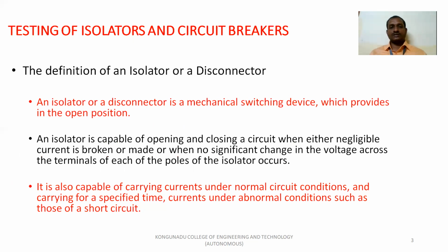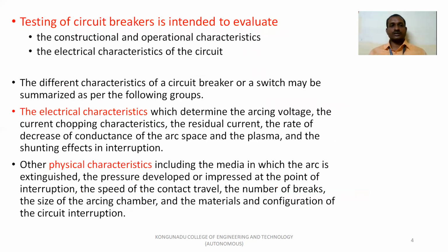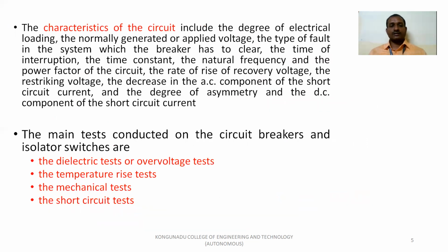An isolator, or disconnector, is a mechanical switch which provides the closed and open positions. It also carries the current during normal conditions and during short circuit conditions. It is used to verify the electrical, constructional and operating characteristics of the equipment. The tests are the dielectric or over voltage test, temperature rise test, mechanical test, and short circuit test.